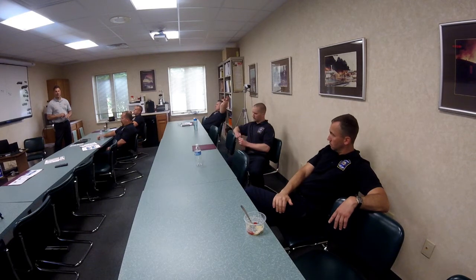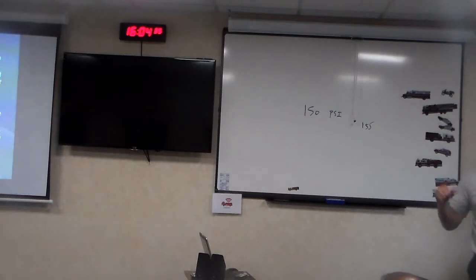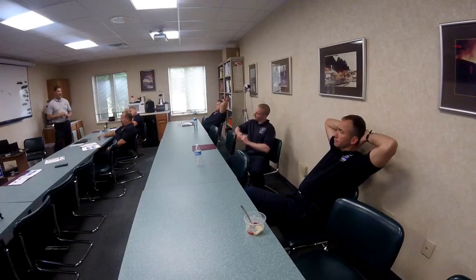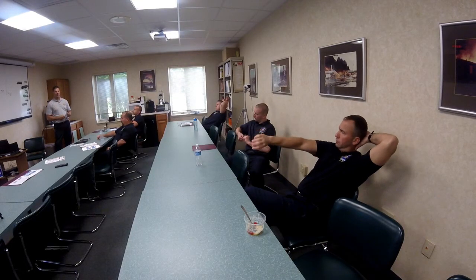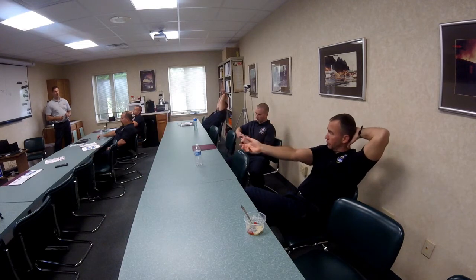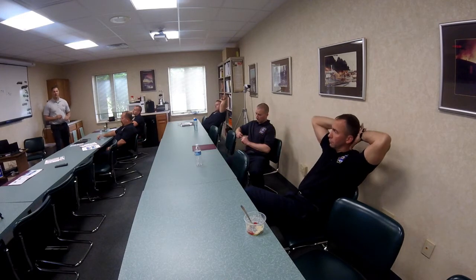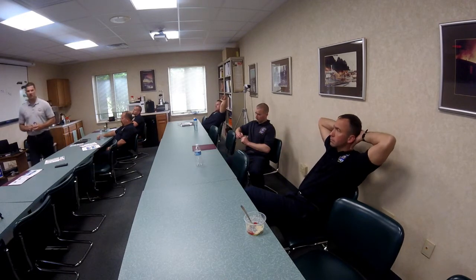Not necessarily. No, you have to throttle up till you get to 155, and that's where you're setting it. If you do what you're doing, you're gonna set it at 150. There's no real change in pressure. If it closes when you turn the knob, and then you go an additional half to 3/4 of a turn, it's gonna be an increase in pressure when that relief valve opens. I'm not sure that's the case. Positive.